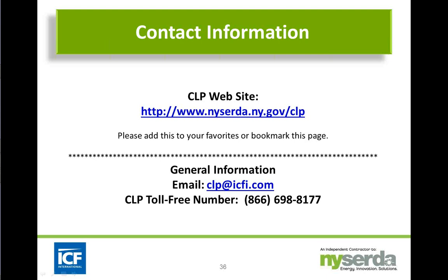Somebody else asked if this can be applied to roadway lighting. We are seeing more and more occupancy sensors used with roadway and exterior lighting. I don't know that I'd use it on street lighting per se, but I've seen applications where people have added this to parking lots and parking lot lighting. The caution is that if you're adding this to HID fixtures, you don't want to turn the fixtures off completely—you need a dimming ballast or bi-level or step dimming ballast so the lights do not go off completely.